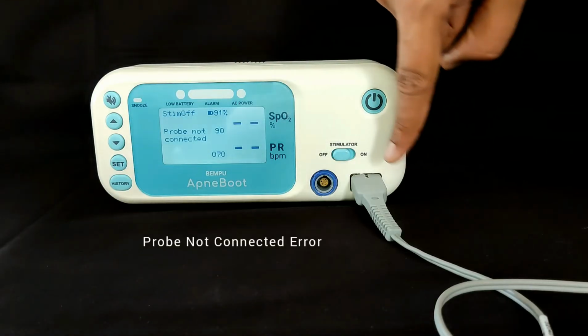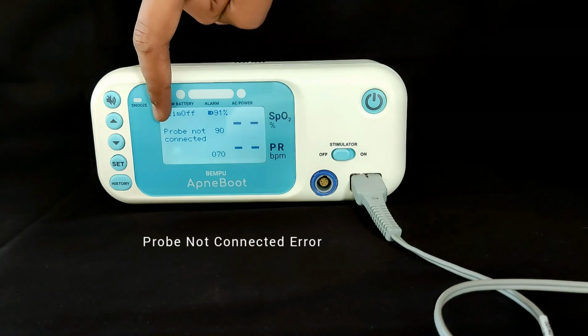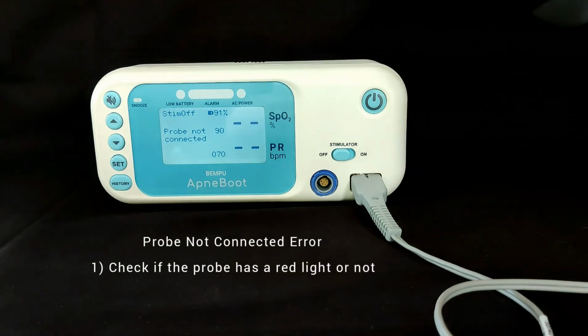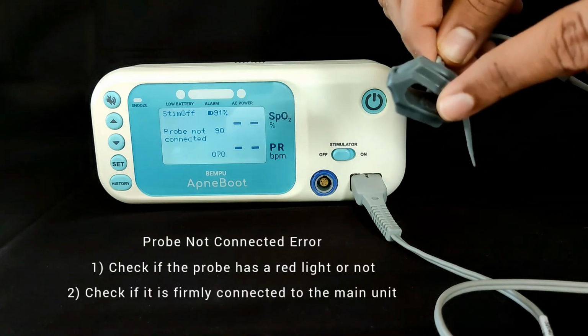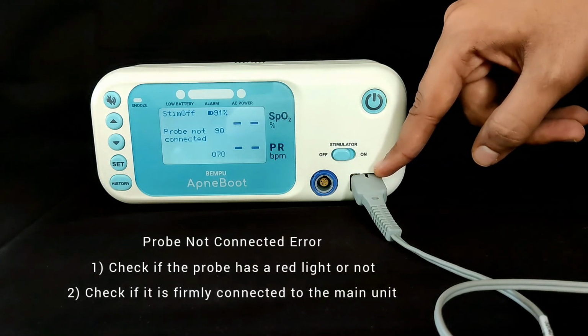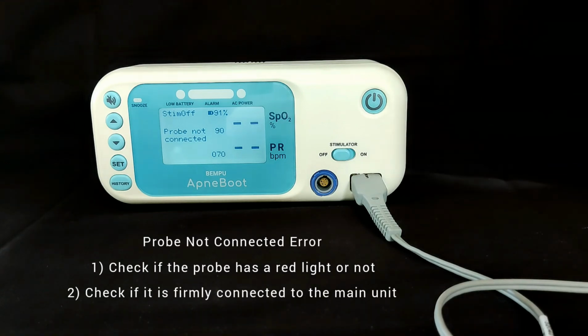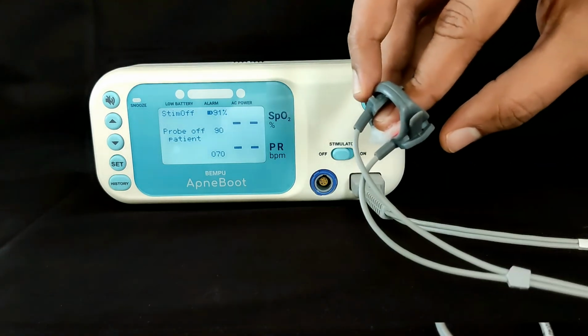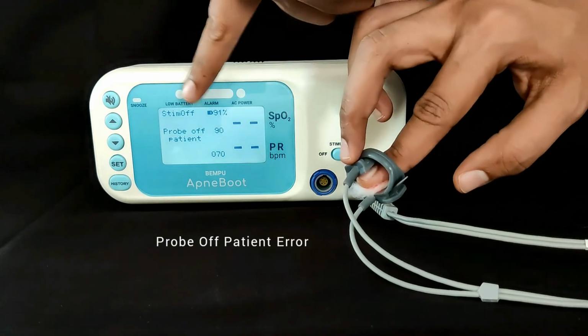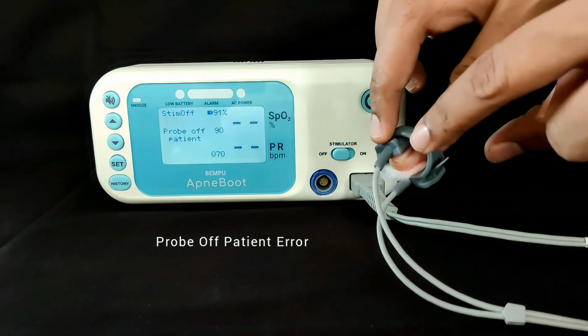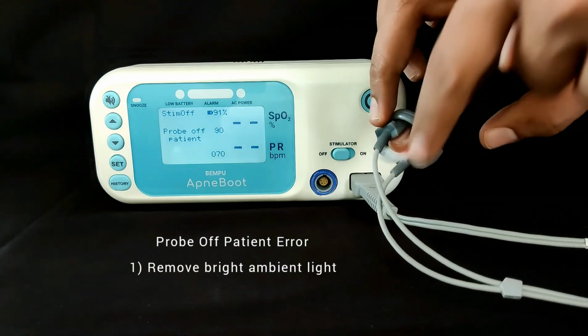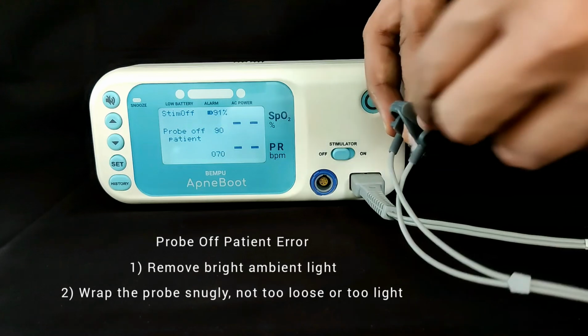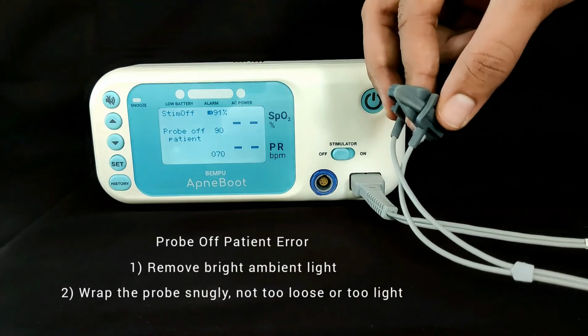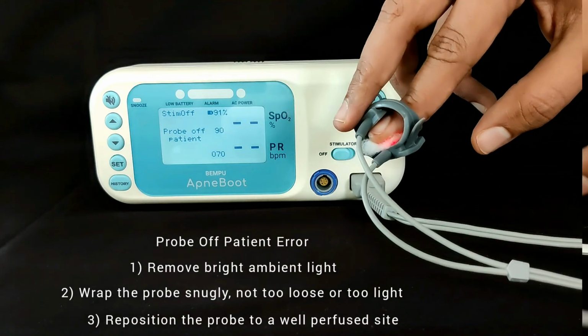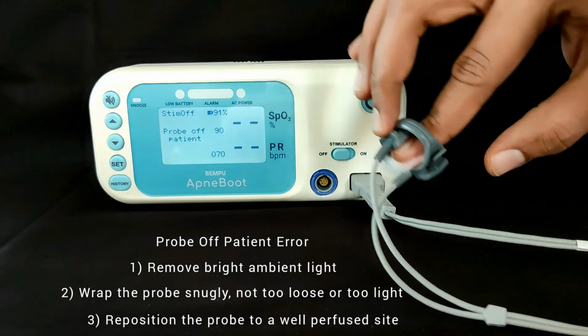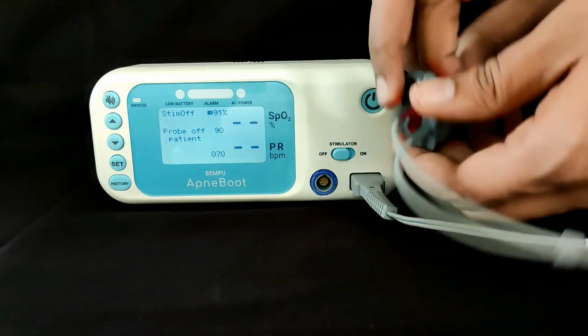If the pulse oximeter probe is connected to the device and it still displays probe not connected, check if the probe's red LED is glowing or not, and check whether it is connected firmly to the main unit. If the issue persists, contact the Bempu customer care to replace the probe. If the device displays probe off patient for a long duration or the readings look inaccurate, check if any bright ambient light is falling on the pulse oximeter probe, whether the probe is placed snugly on the baby, not too tight or too loose, and check if the site is well perfused and reposition the probe to another site if needed. If the issue persists, please contact the Bempu customer care.